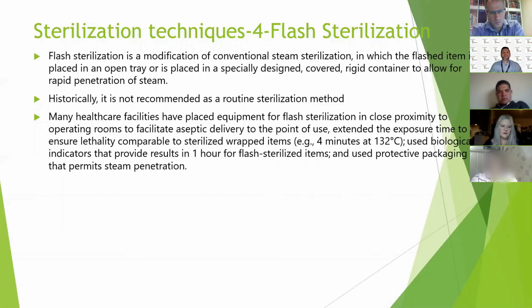Flash sterilization is a new technique. It's not that new, but it's new. It's a modification of the conventional steam sterilization, whereby it is put in a rigid container with its covering, and then it is allowed to quickly clean. And this is usually used when you dropped something and you want it cleaned very, very quickly. They call it the quick cycle. So if you speak to your SSD, this is how they do it, but they don't advocate it for routine use. It is something only for emergencies, if it is needed.